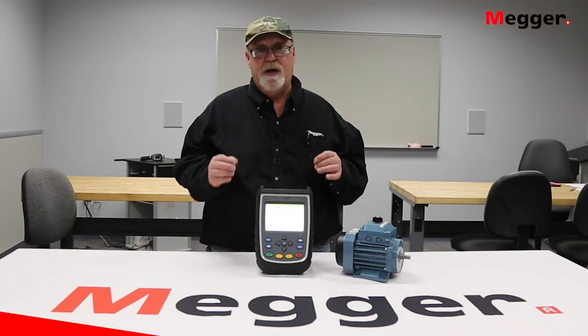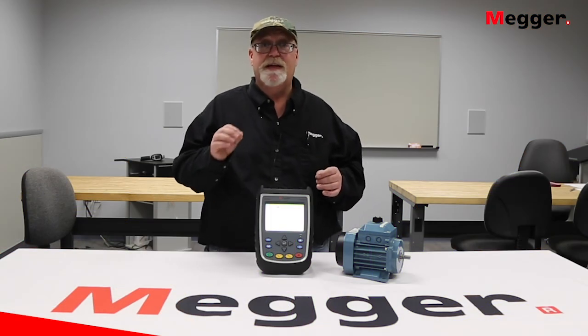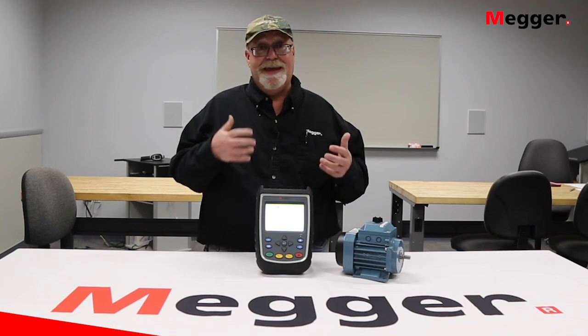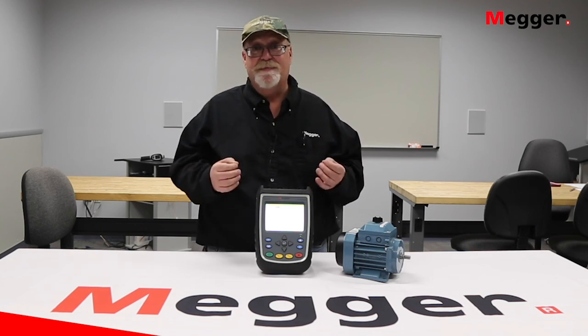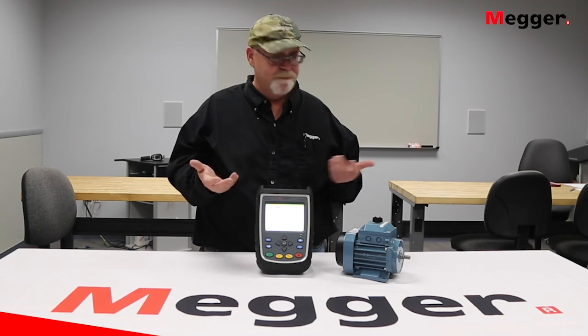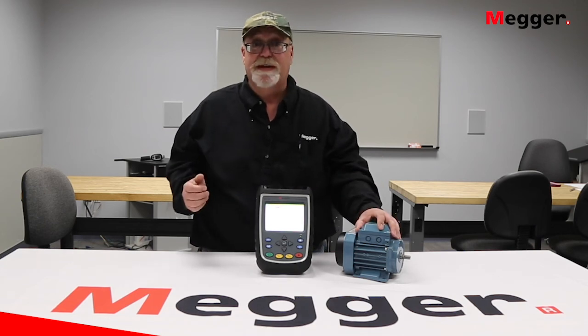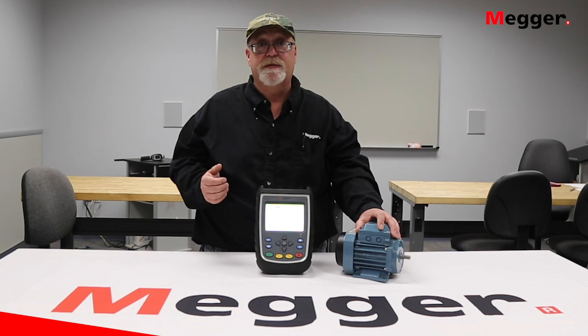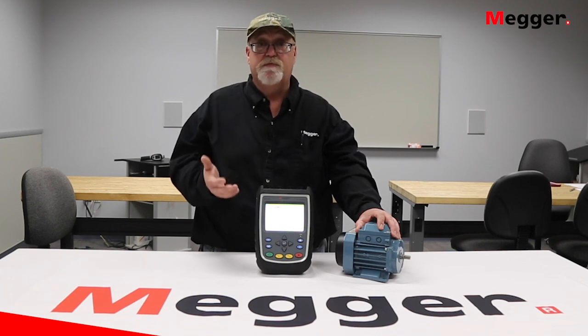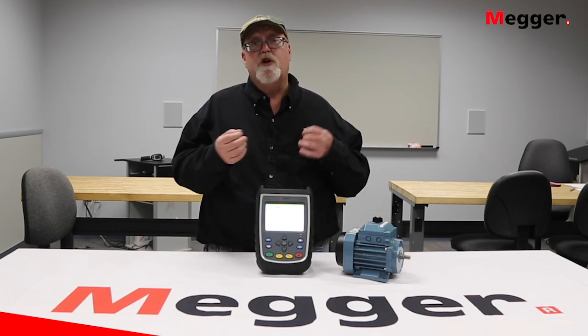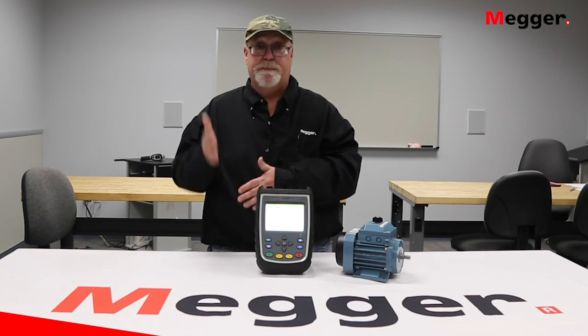Each time they turn on, they draw a very high level of inrush current, and motors will draw several times their full load current when they're turning on. Even small motors can draw up to 6 to 10 times their normal current on an inrush. These large currents can actually lead to voltage dips.